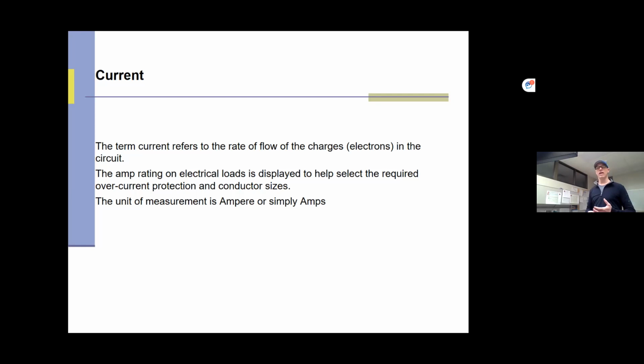That's a really good one. When I look and see my amperage starts to drop a bit, that usually tells me that inside that pump, something's worn out. Something's not restricting the flow as much, which means there's got to be either a problem with the check valve or a problem with the impeller.